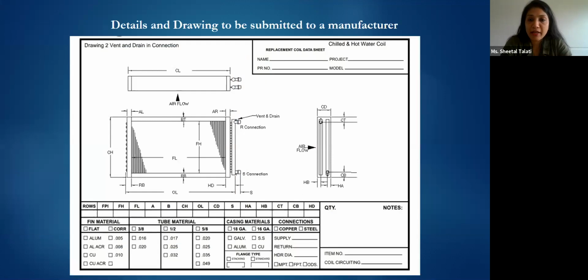This is the final drawing that is prepared or is expected out of the client. You measure the fin to fin length first, then you give us the overall dimension with the end plates or the side frames, the OD of the pipe. This is a chilled water diagram that I've shown in the presentation. The header pipe OD is also very important, whether it's a 2-inch pipe and what kind of end connection you want, whether it's a left-hand side circuit or a right-hand side circuit. What kind of casing material do you require, whether it's galvanized iron, aluminum, SS, copper. Even the fin material and the fins per inch. Do count fins per inch and do mention it in your diagram.